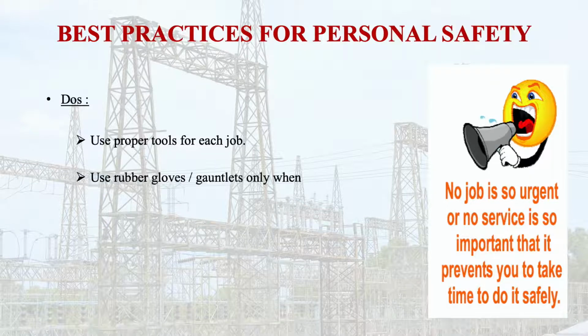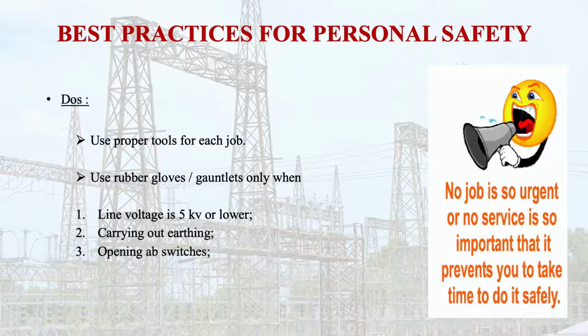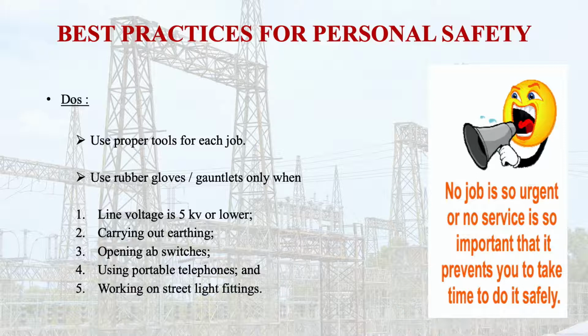Use rubber gloves and gauntlets only when line voltage is 5 kilovolt or lower, for low voltages. When carrying out earthing, one should use rubber gloves, also when opening AB switches, using a portable telephone, and working on street light fittings.